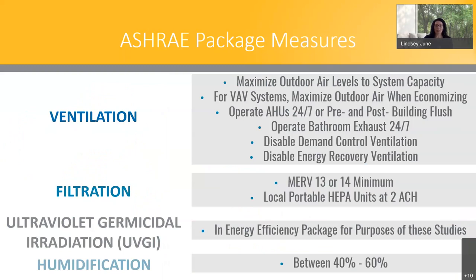So for ventilation, it included maximizing outdoor air levels as much as the system's cooling and heating coils can handle. Where there are VAV systems, maximizing outdoor air when economizing. Operating air handling units 24/7 or performing a pre and post building occupancy flush. Running bathroom exhaust 24/7 and disabling demand control ventilation or energy recovery ventilation if a potential for cross-contamination exists. For filtration, the minimum was MERV 13 or 14, and local HEPA portable units operating at 2 ACH. Humidification, the target was between 40 and 60% relative humidity.